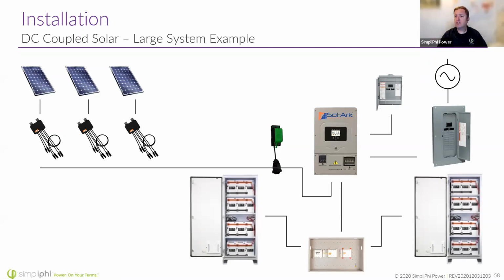Really quickly, here's a picture of what it looks like to see a system. We've got our Sol-Ark, we have our Tigo TS4 rapid shutdowns, here's our Tigo transmitter sending that keep-alive signal, here's our critical loads panel, here's our non-backed-up loads panel, and grid feeding into the Sol-Ark so we can backfeed to the grid.